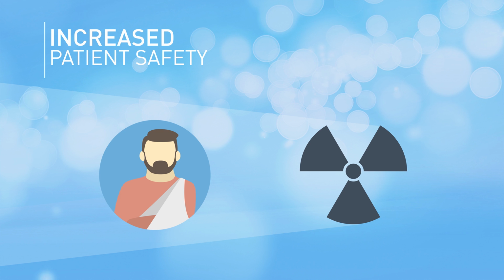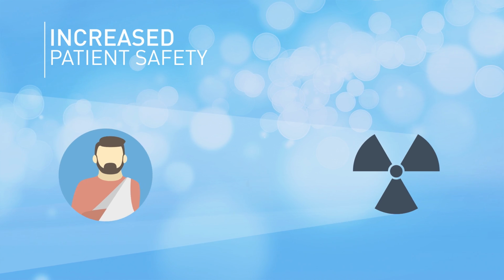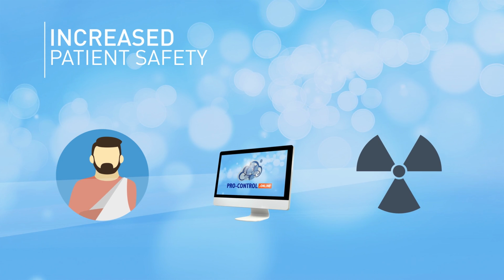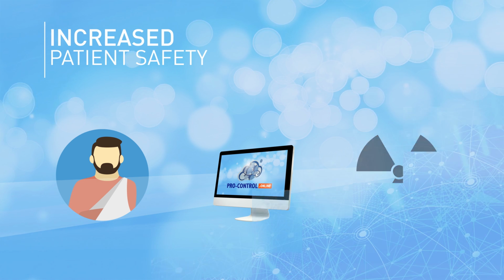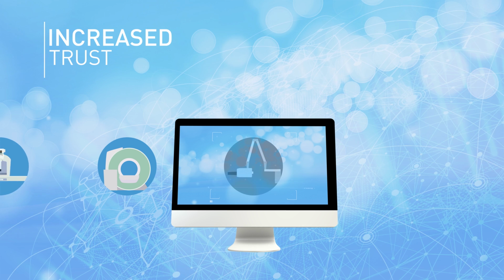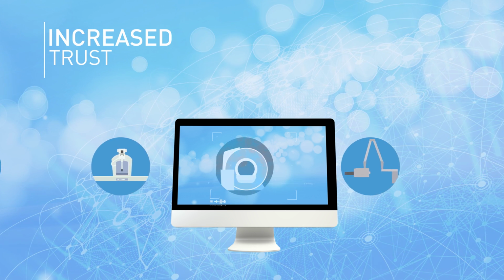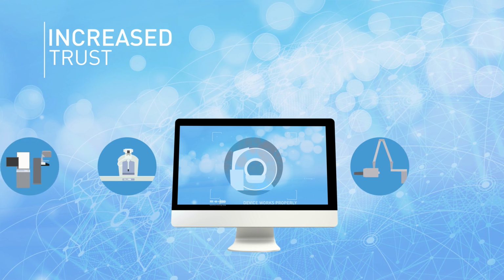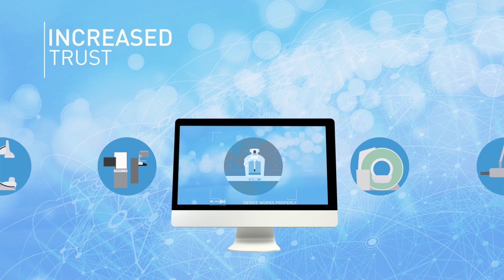Increased patient safety, the ALARA principle. Because all devices for image diagnostics are under control, there is no risk of excessive radiation or wrong diagnosis. Increased trust in the proper operation of diagnostic devices: objective tests show whether a device works properly or not, with any defects easily noticed, diagnosed, and corrected.